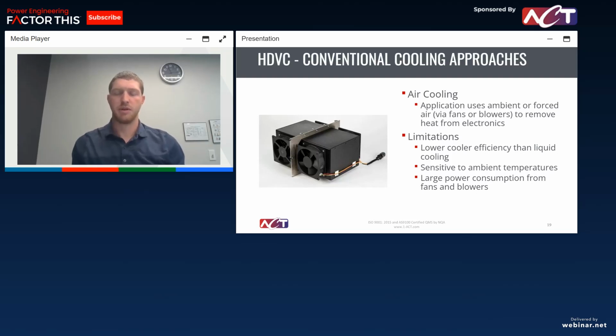So just taking a look at some of those conventional approaches. First here being air cooling. This is, as many of you know, just an application where we use ambient or forced air. We're taking heat away from the electronics and ultimately rejecting it to that air. The advantages here are that it's usually very easy to implement, a pretty simple setup, and if you have a low power situation or application, it can be very effective.